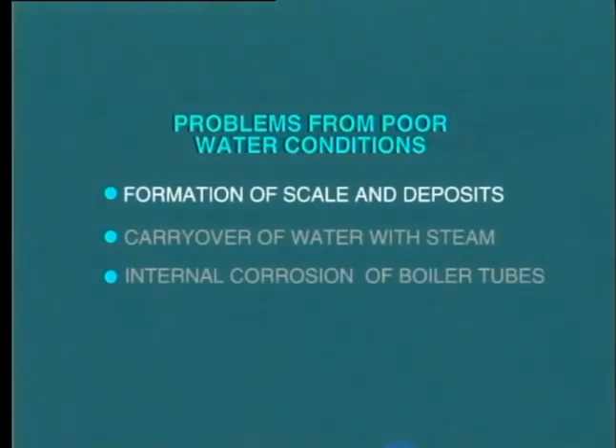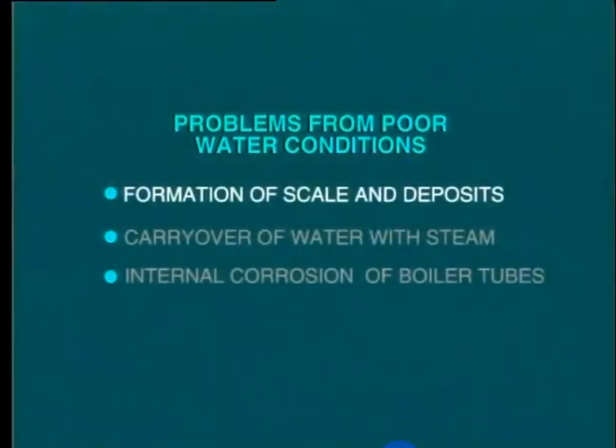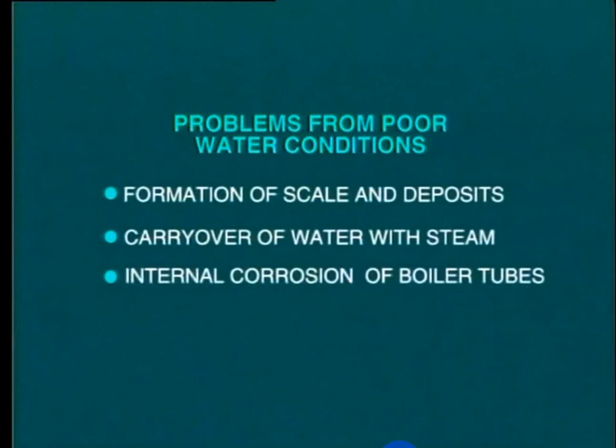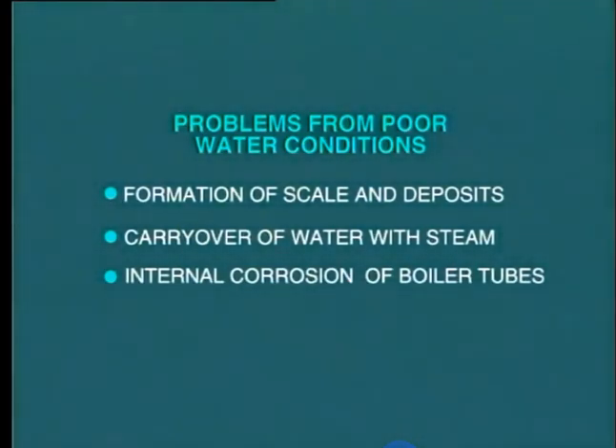So what is it exactly that we are protecting the boiler against? What are the problems that can arise as a result of feeding impure water into the boiler? The principal problems arising from poor water conditioning are: the formation of scale and deposits inside boiler tubes, the carryover of water with the steam, and internal corrosion causing wastage of boiler tubes.